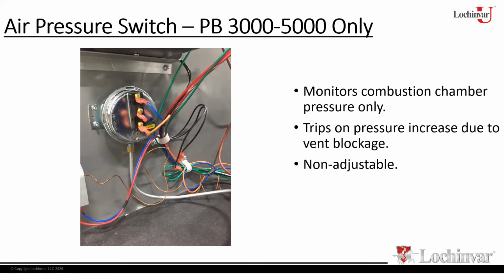The 3 to the 5s, however, would not. So that's the reason they get the switch. I have to have the switch there to pass the test, if you will. So you'll see various products that will have pressure switches and some that won't. A good example, the FTXL models do not have a pressure switch on them because they all will shut down before the combustion gets to the point where it's bad. So I don't need a pressure switch there, but here we do. So again, 3 million to 5 million has to have the switch. And in this case, it's positive pressure only. It's a normally closed set of contacts, a block vent switch.